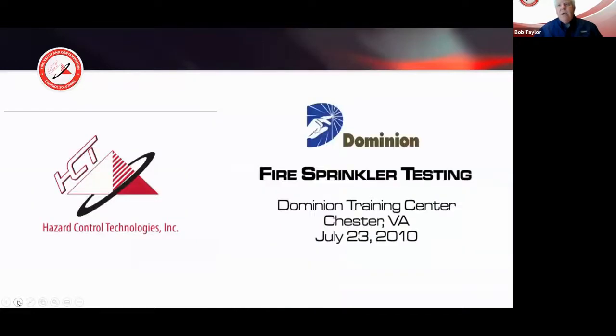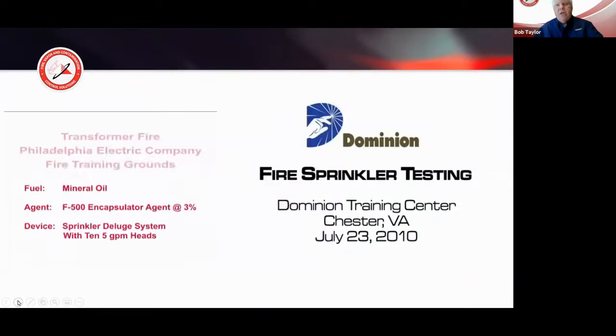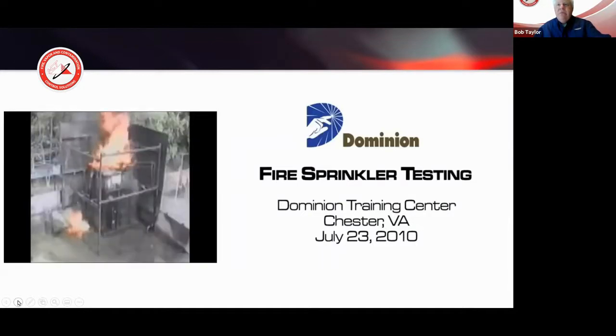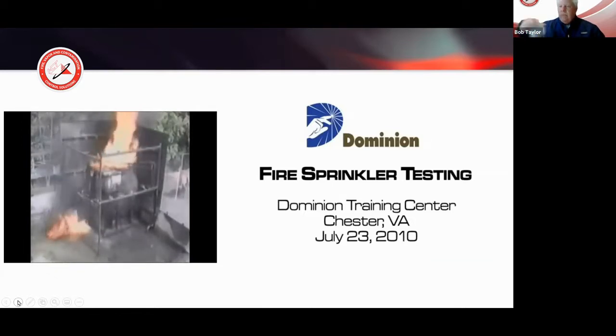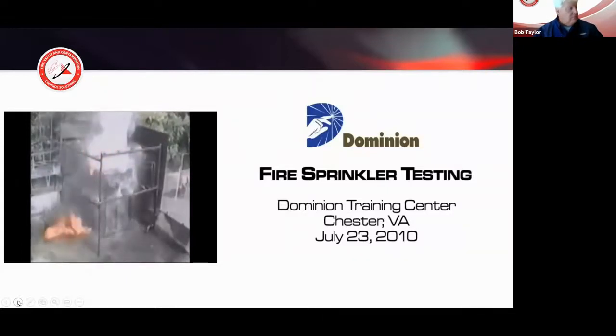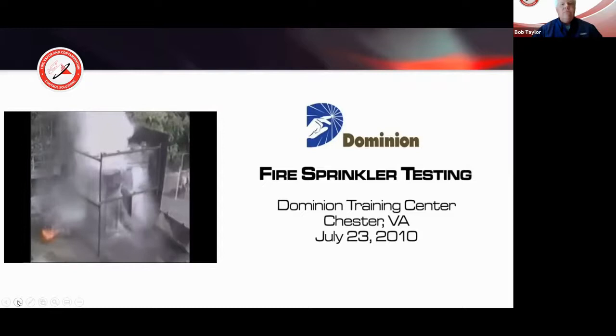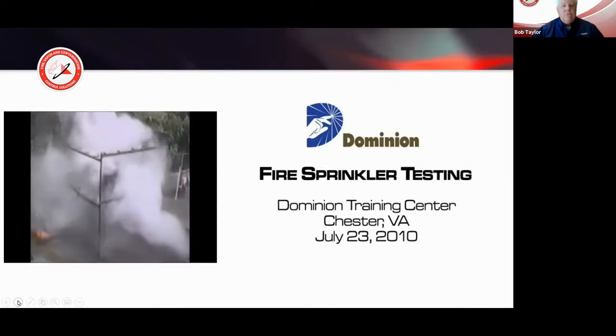Hazard Control Technologies presents some testing of the F500 encapsulator technology that we'd like to share with you. This is being delivered at 3% solution at the Philadelphia Electric Company fire training grounds, where F500 is being used to extinguish an electrical transformer fire. F500 is fed at 3% into the sprinkler deluge system utilizing ten 5-gallon-per-minute heads. The fire is quickly knocked down, including the running surface fire, by the indirect spray from the heads.